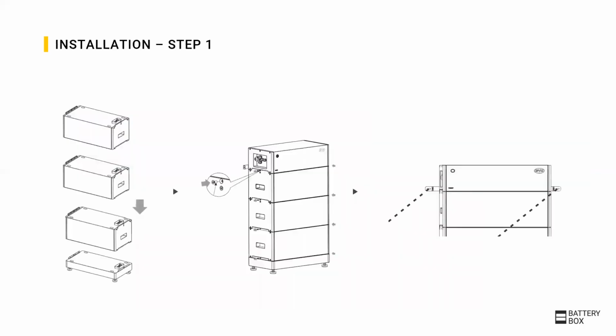With those limitations in mind, we will look into the installation, which is held as simple as possible and which is shown in principle on this page. The base is placed on the floor and the modules are simply stacked on top without any internal cabling. The modules can then be fixed with screws on top of each other. Finally, the BCU is placed on the top module and attached to the wall.